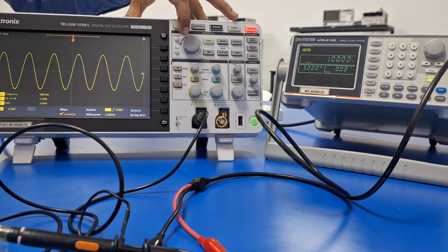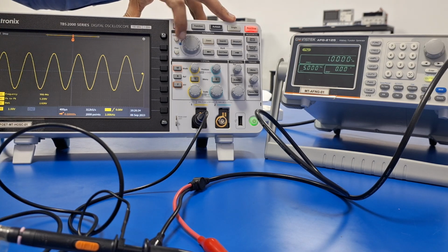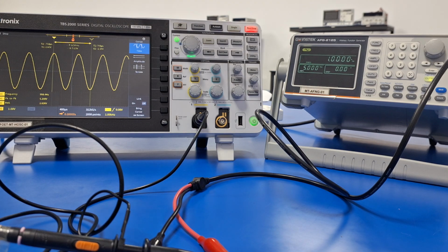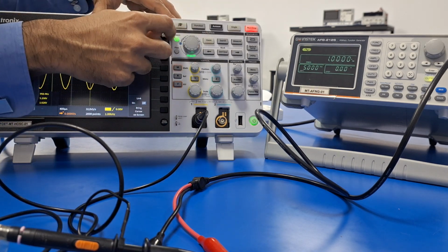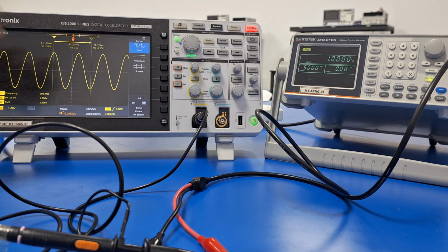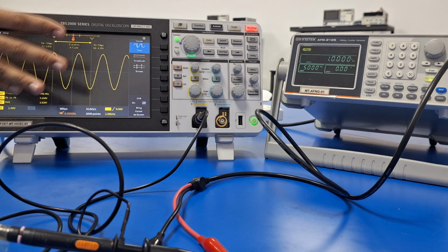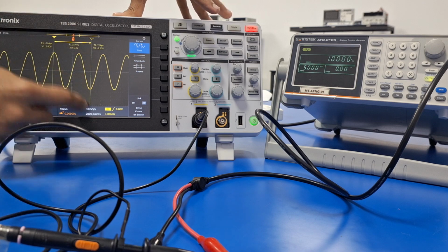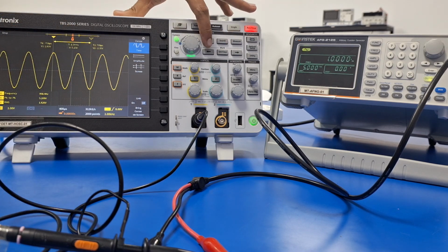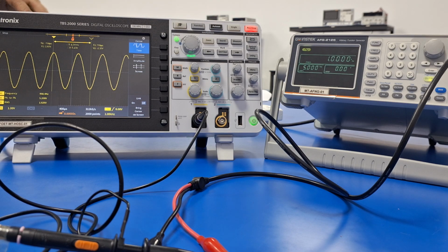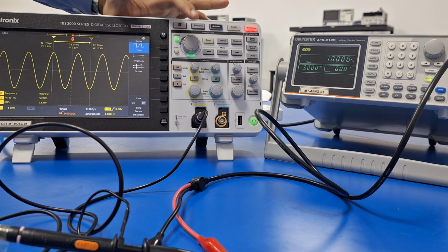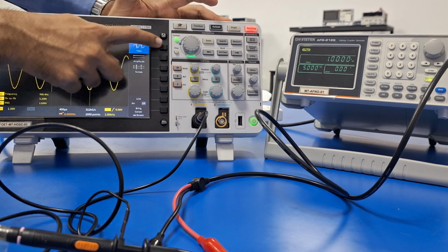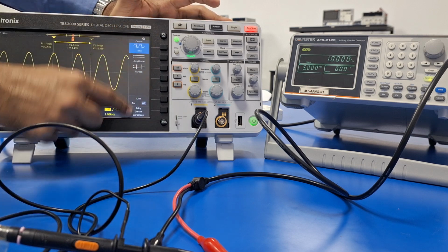So the more advanced the oscilloscope is, the more precise the cursor commands are. So you can go to the cursor menu. Now in this oscilloscope I have a separate button for the cursor, but in certain oscilloscopes it might be buried under a menu. Again, refer the manual to figure it out. And after selecting the cursor, you can see some lines started to appear, and these are actually the cursor lines. So there are 4 lines in total. You can have up to 4 lines, 2 lines for the y-axis and 2 lines for the x-axis. So you can select them from these menus that are appearing in the edge of the screen.